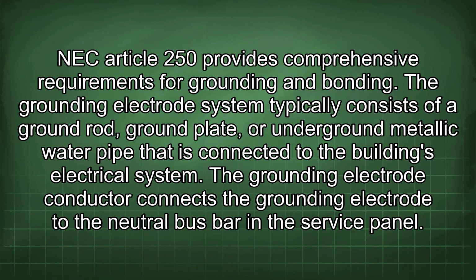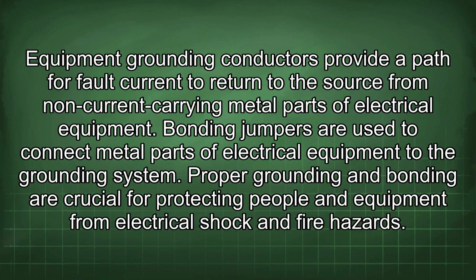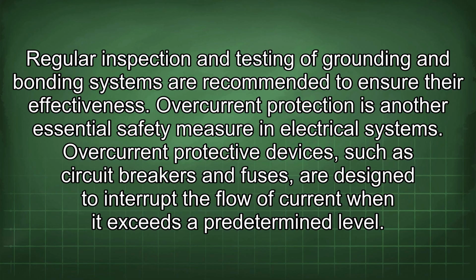The grounding electrode system typically consists of a ground rod, ground plate, or underground metallic water pipe that is connected to the building's electrical system. The grounding electrode conductor connects the grounding electrode to the neutral bus bar in the service panel. Equipment grounding conductors provide a path for fault current to return to the source from non-current carrying metal parts of electrical equipment. Bonding jumpers are used to connect metal parts of electrical equipment to the grounding system. Proper grounding and bonding are crucial for protecting people and equipment from electrical shock and fire hazards. Regular inspection and testing of grounding and bonding systems are recommended to ensure their effectiveness.